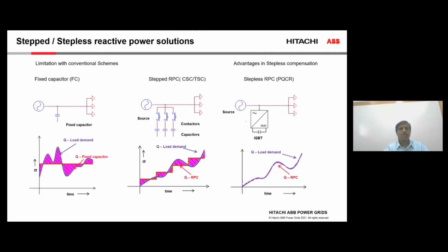Then what kind of solutions do we have when it comes to the power quality solution, especially the reactive power solutions? We traditionally used to simply apply a fixed capacitor in parallel with load, and this fixed capacitor gave capacitive power which cancels the inductive power responsible for lagging power factor, and it used to correct the system. Then we also had CSC and TSC, which means contactor switched capacitors and thyristor switched capacitors. Now these solutions could correct the power factor when you have a varying load, but this correction used to have steps. Then the latest technology that is there is a stepless reactive power compensator, where however the load profile changes, and however fast it is changing, our compensator also reacts at the same speed and corrects the power factor whenever it is happening, at whatever speed. These are the three technologies that are available to us.